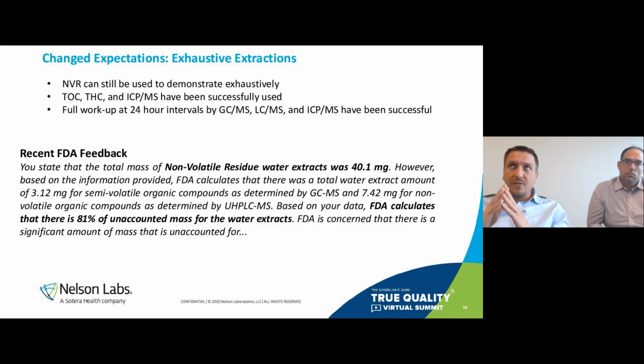In truth, from the perspective of chemistry, these two amounts really shouldn't match. So if you do an NVR and that matches exactly what you measure by GCMS and LCMS, then I would be highly, highly suspicious that something's up. Those two numbers really shouldn't match. But still, we have to be ready to explain that if you do exhaustive extractions and submit this to the FDA. I think that better than NVR is to use things like TOC, THC, and ICP-MS to demonstrate exhaustiveness.